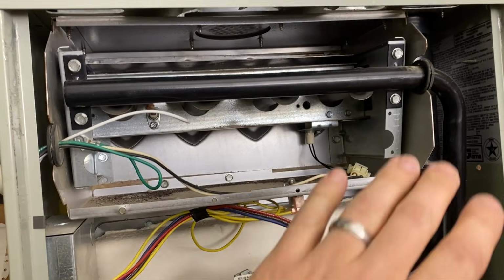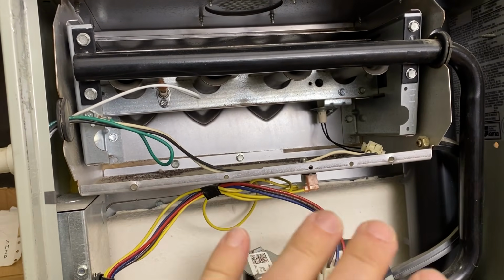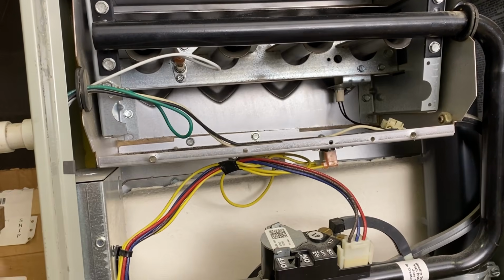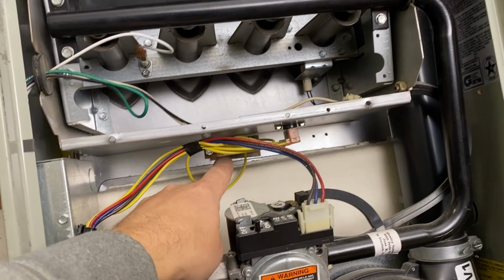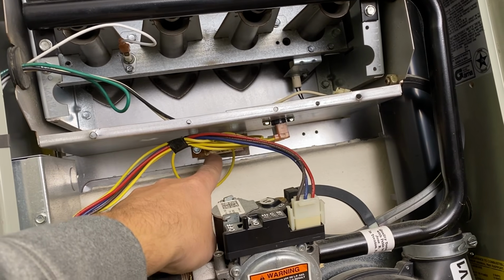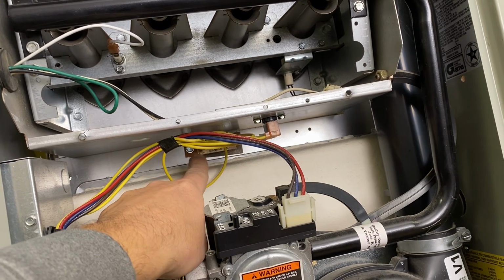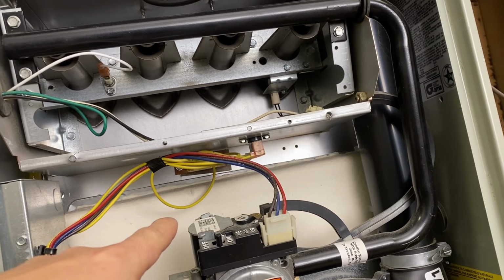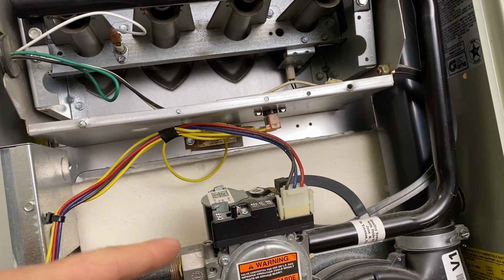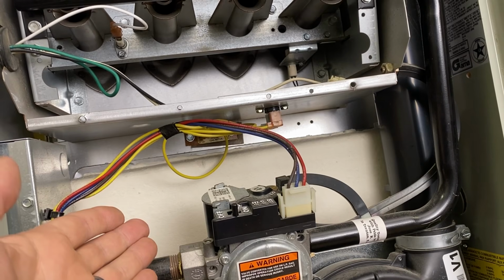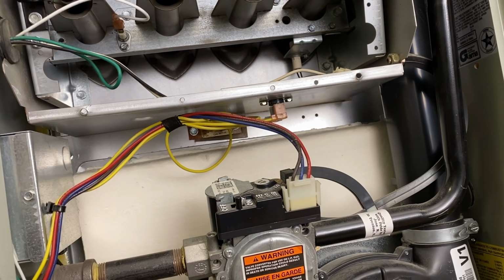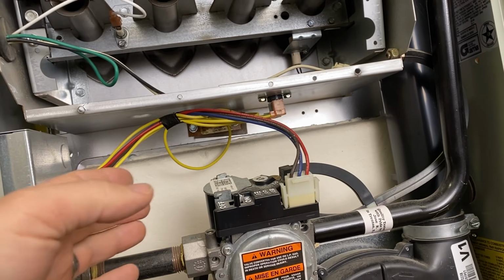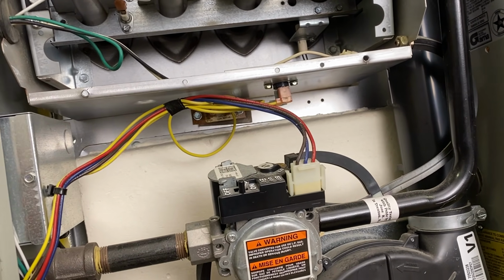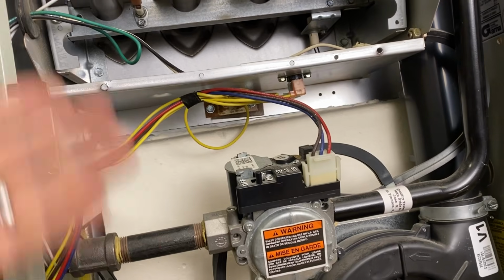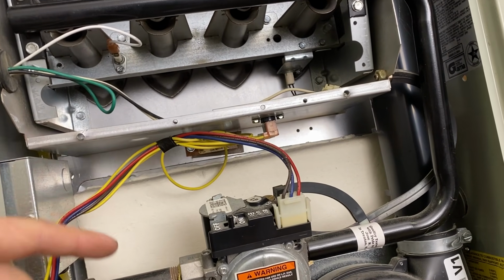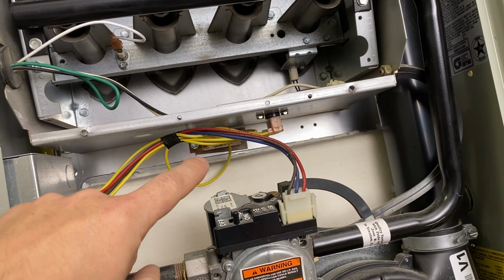If your furnace gets past this point, if its burners are all running and it fires up for a little while, what's going to happen next is it's going to sense the temperature of the heat exchanger. So this is actually what's called a limit. Generally, it has a low and a high. There's usually a low and a high limit. Some of them are combined into one sensor, some of them are separate. But the low sensor, basically, once it gets up to a certain temperature, then the main blower will kick on and it will heat your home. If it overheats, meaning again, if there's a clog or if your blower isn't working right or something like that, it's not taking the heat off of the pipes in there, it gets too hot, has a high limit, and that will also shut off.